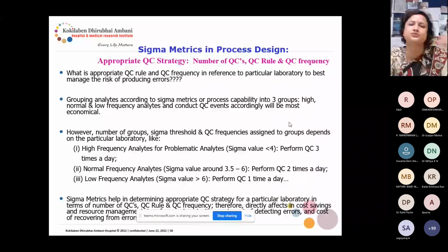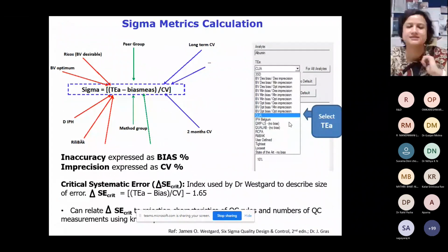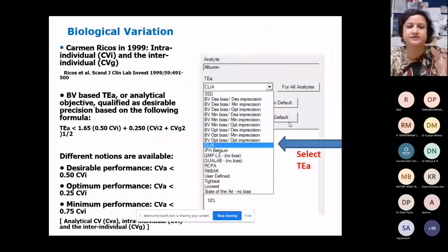We can customize the number of QCs, QC rules, and QC frequency based on high frequency analytes, normal frequency analytes, and low frequency analytes. This is the formula for that. Total allowable error we can get from CLIA, from biological variation, or from others like Ricos and so on. Bias we get from the peer group or method group. For the sigma metric calculation, we can take a 2-month CV, quarterly CV, or long-term CV percentage. So this is how total allowable error is selected.